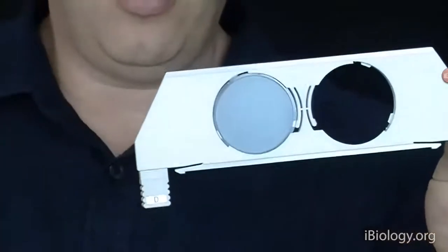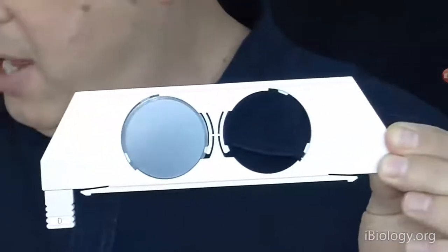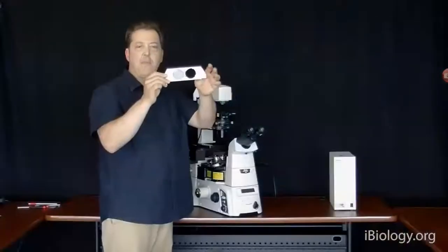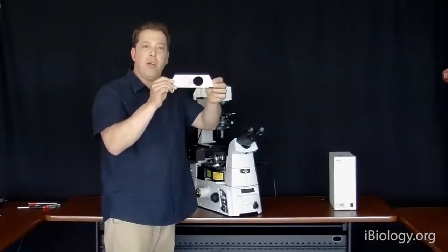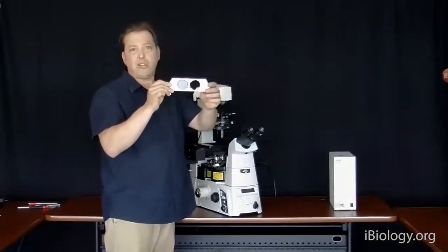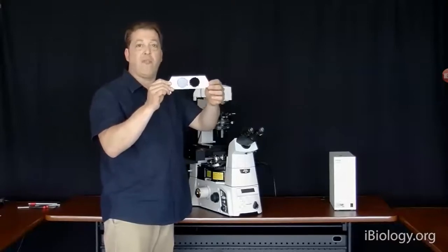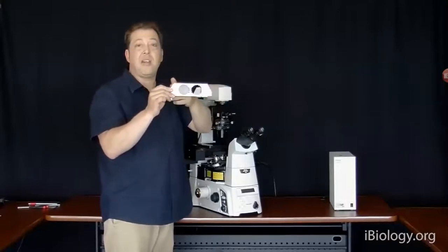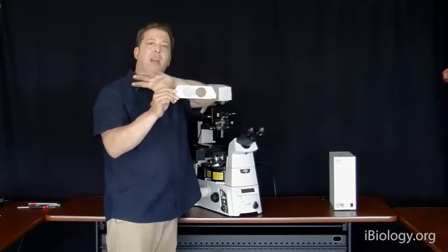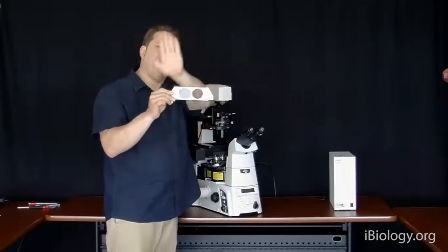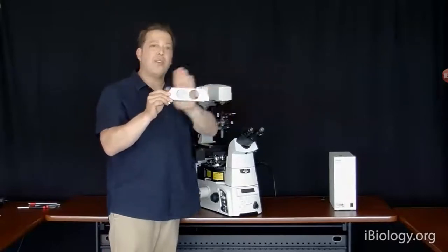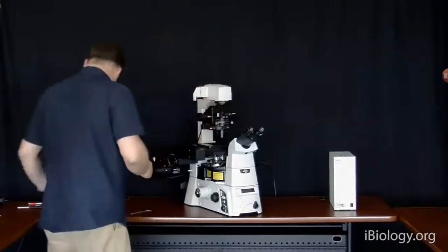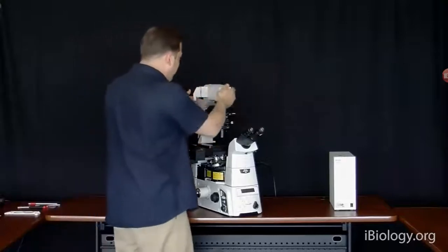And this diffuser is just a frosted piece of glass or plastic, and it breaks down those harsh edges of the filament in the bulb and softens it. We also use a technique called a fly eye lens that, instead of having a single filament, will make thousands of images of that filament doing the same thing, basically diffusing it throughout the field of view and giving you very even illumination. And we have several filter holders.